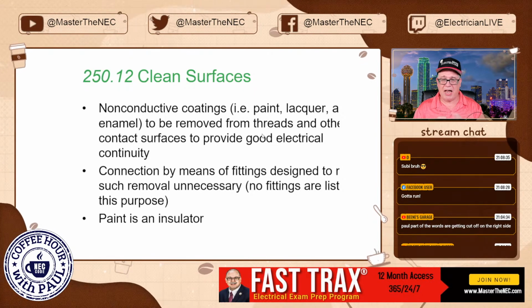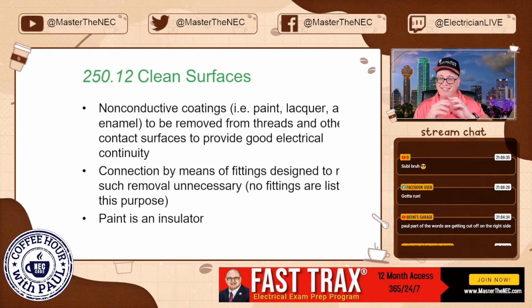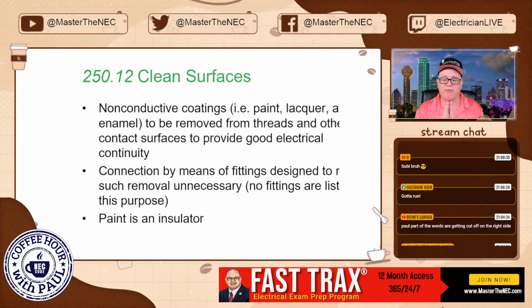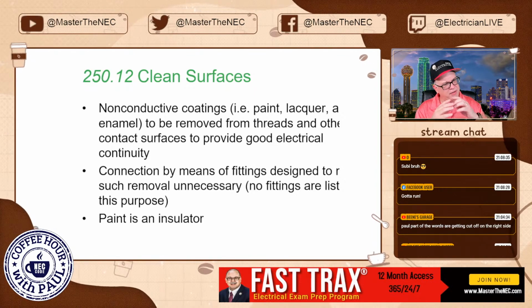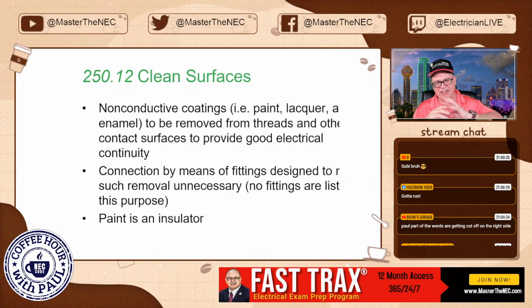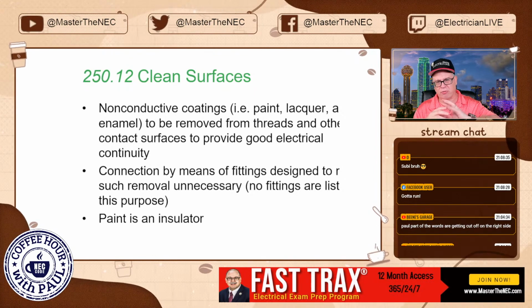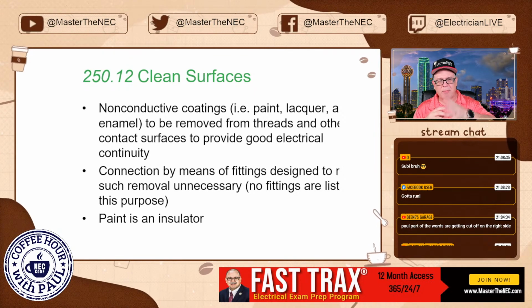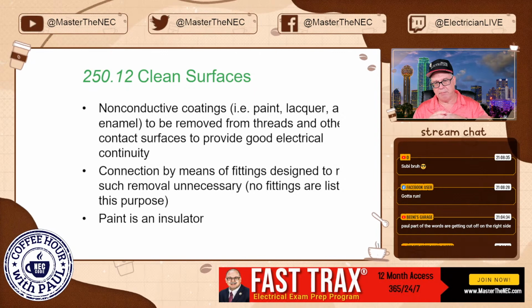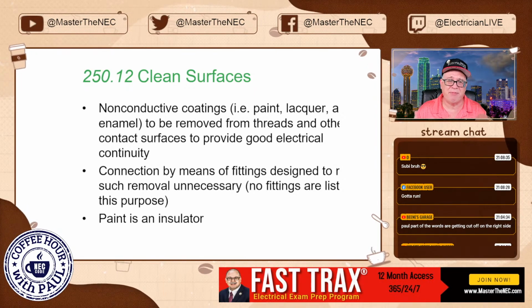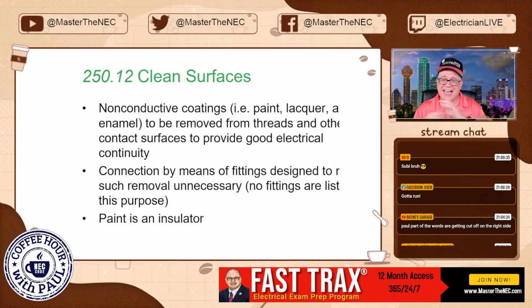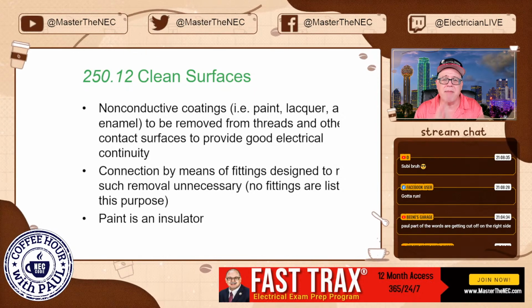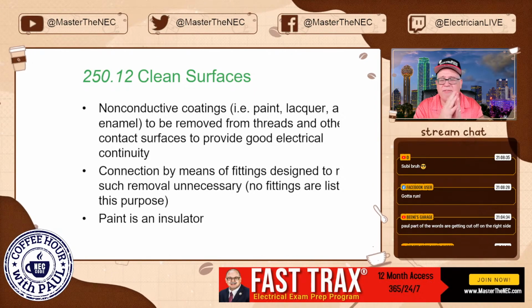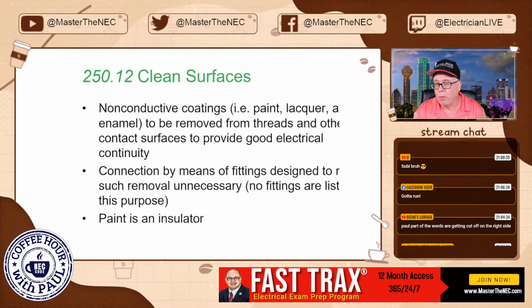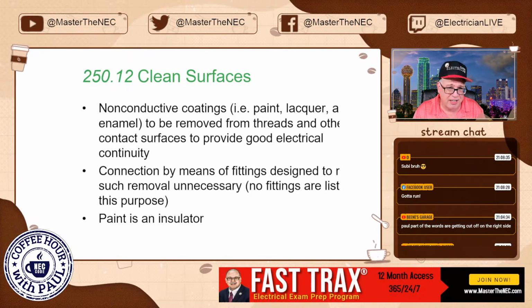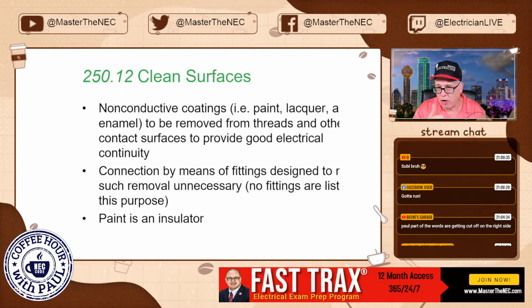Now, you could have a lock nut that actually is, there's 2 different types of lock nuts, right? There's the flat ones, and then there's the ones that have a bit of a hook bill on them. Those are designed to cut into the actual cabinet, okay? Now that's going to make a connection for you. But this is reminding you that if you have any type of paint or anything on your threads, you got to clean it off. We need that metal-to-metal contact. We need everything to be intact. Remember, we need that low impedance, intentionally constructed, effective ground fault current path.